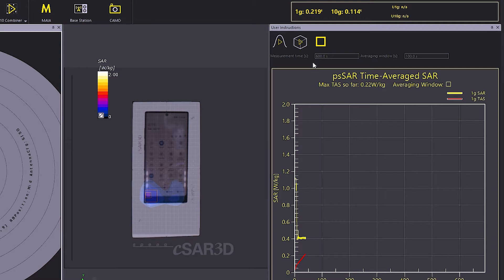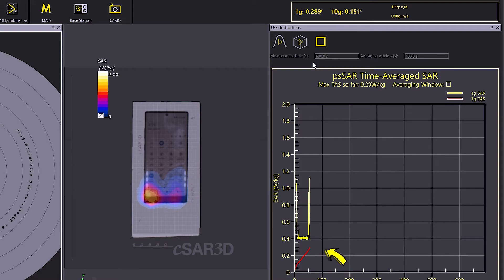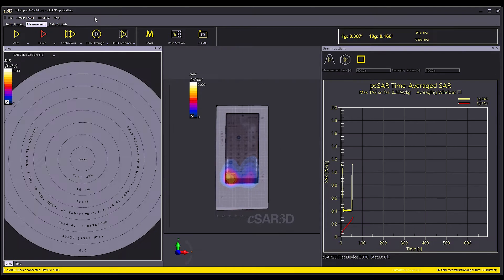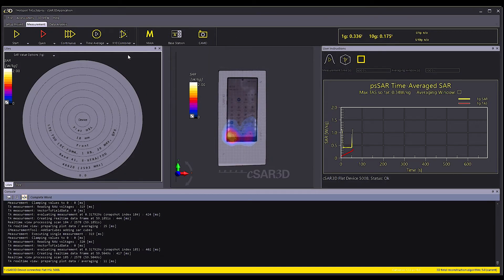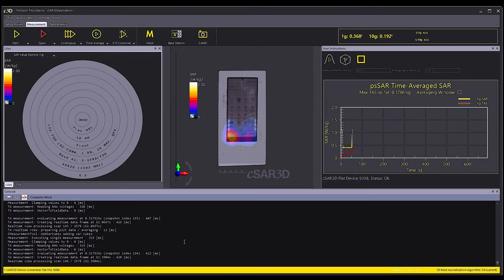On the TAS window, we see the plot of instantaneous SAR values versus time in seconds. The thick red line on the plot shows the 1 gram TAS value. All these values are updated 3 times per second.